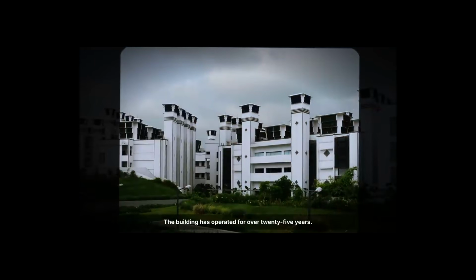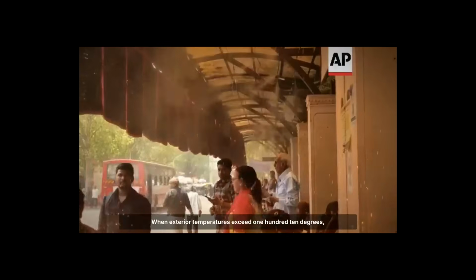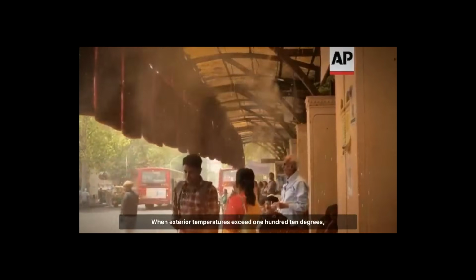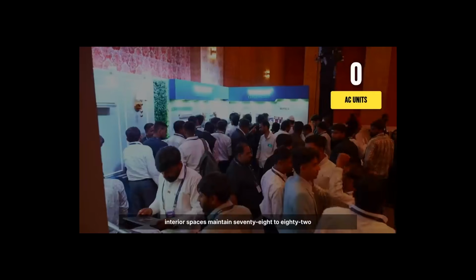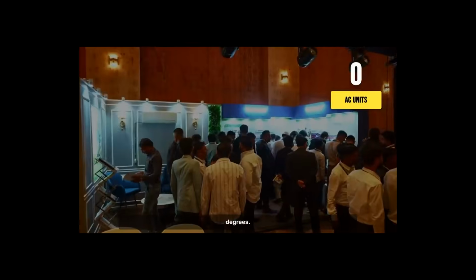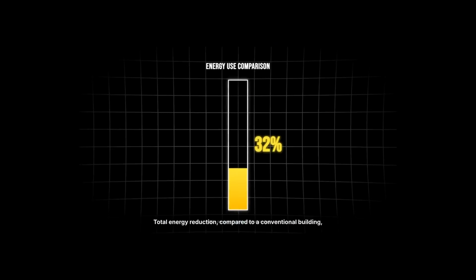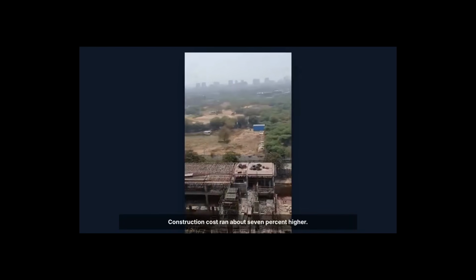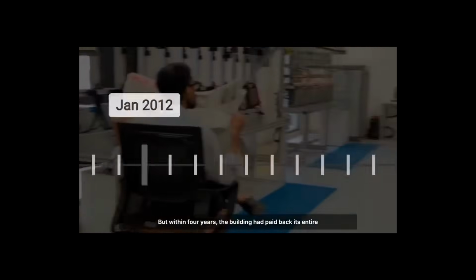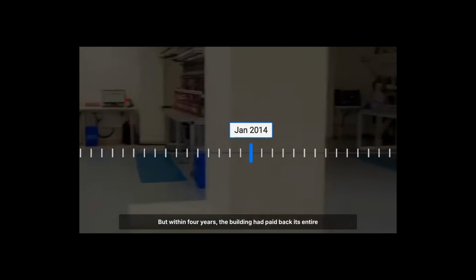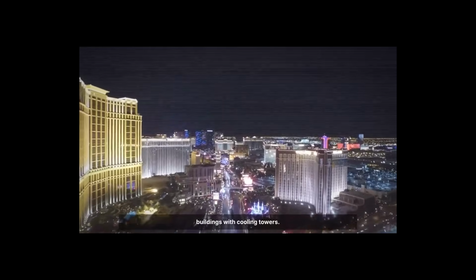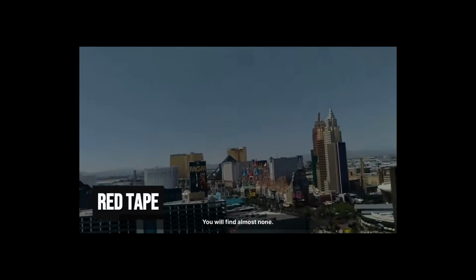The building has operated for over 25 years. When exterior temperatures exceed 110 degrees, interior spaces maintain 78 to 82 degrees. Total energy reduction compared to a conventional building measures 68%. Construction cost ran about 7% higher, but within 4 years, the building had paid back its entire construction premium. Yet drive through Phoenix or Las Vegas today and count the buildings with cooling towers. You will find almost none.